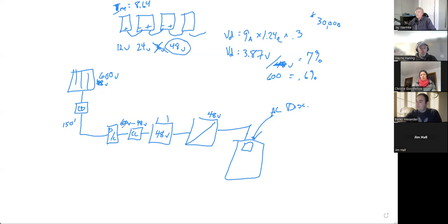So that is a good solution. And it turns out these MPPT charge controllers don't really cost more money than the old charge controllers. So this is going to be your solution. You're going to put in a buck boost charge controller or an MPPT charge controller. The reason I don't like the term MPPT is, remember, the MPPT is the maximum power point tracking. So that's keeping this operating at the sweet spot. Well, every charge controller has an MPPT built into it. So calling this an MPPT charge controller is confusing because they all have it.